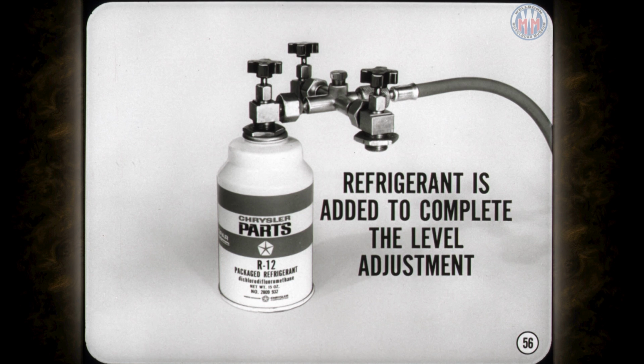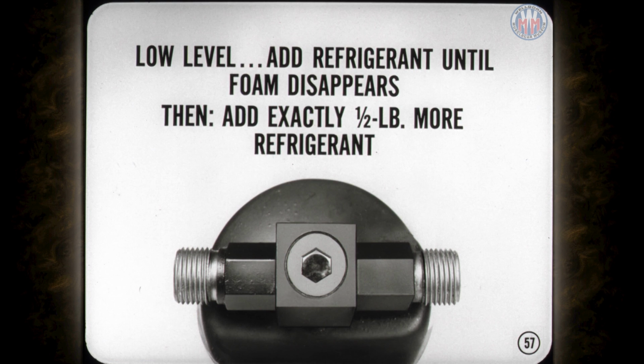Fred, earlier you mentioned that the refrigerant level can be high as well as low. How do you get it right? Well, in either case, some refrigerant is added to complete the level adjustment. So you leave the gauges connected and arrange a refrigerant source for system charging. Now, to correct a low refrigerant level, you add refrigerant until the foam disappears from the sight glass. Then you add exactly 1/2 pound more to get the correct level.